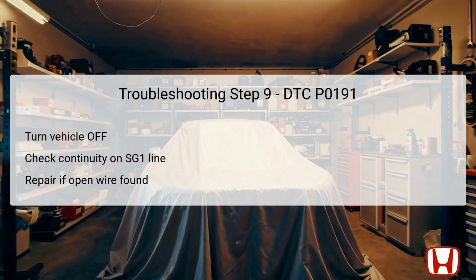If continuity is present, it signifies that the SG1 line is intact. In this scenario, we would then review any technical service information related to associated DTCs for further understanding of symptoms. If continuity is absent, this points towards an open wire issue within the SG1 line itself. Such faults necessitate detailed repairs to restore proper connection and function of the sensor.